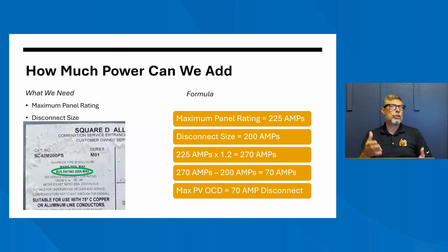So those of you that are kind of new to home inspection, we always say, take a picture of the label. Well, the label actually tells us a whole bunch of things. But for this standpoint, what we're looking for is the bus rating. If you look at the bus picture there, the rating of the bus bar says the bus rating on this one is 225 amps. We can take that bus bar up to 120% of that rating. So the way we would do that is you're going to take your 225 max rating, multiply it times 1.2, and that tells us that we can put a maximum of 270 amps into that bus safely.